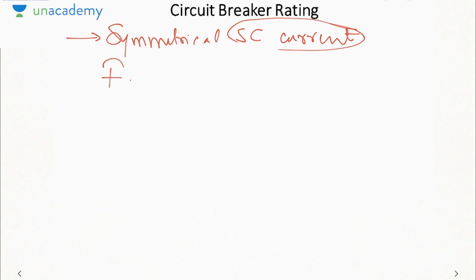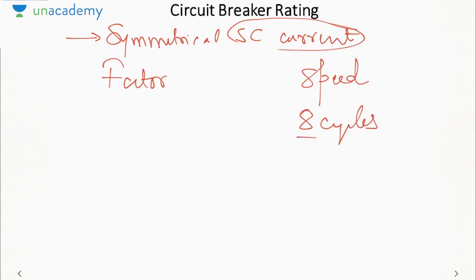As I told you, mostly you will open in the transient region and not in the subtransient or the steady state. Now if you take 8 cycles speed, that is, the time is greater than 8 cycles, so it is taking a very large time. In 8 cycles, the DC offset current will almost have decayed to 0. If it has decayed to 0, then the only current that remains is the symmetrical short circuit current. So we multiply it by a factor of 1. No need to multiply it by any other factor because the DC offset current is almost 0.